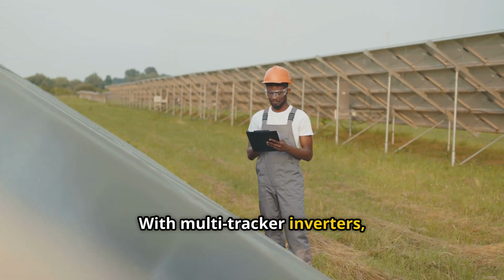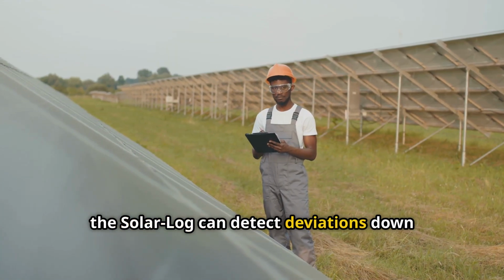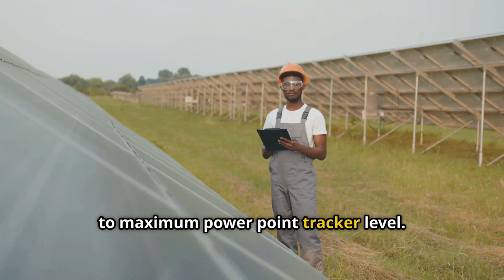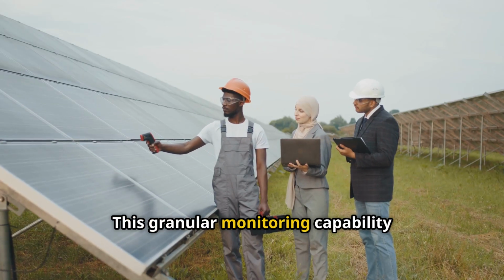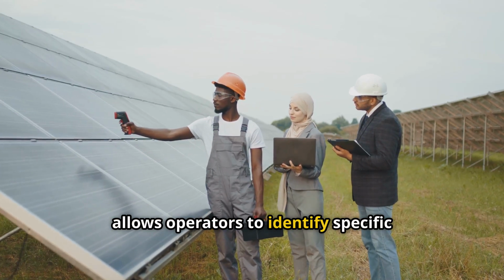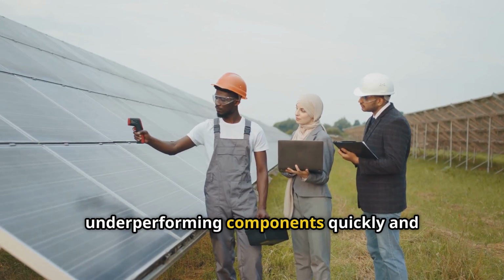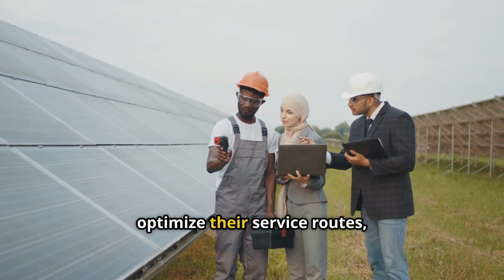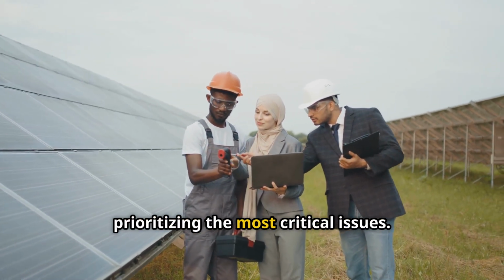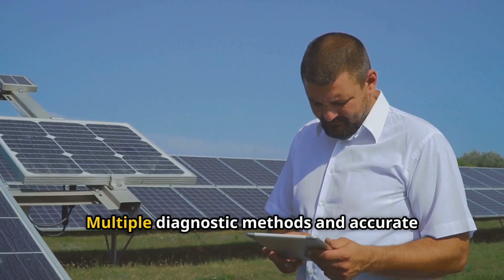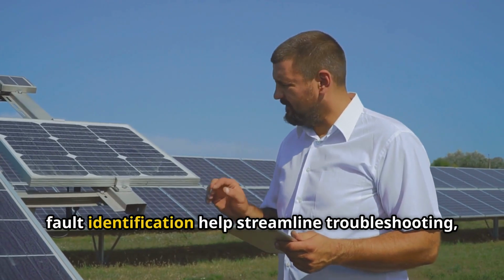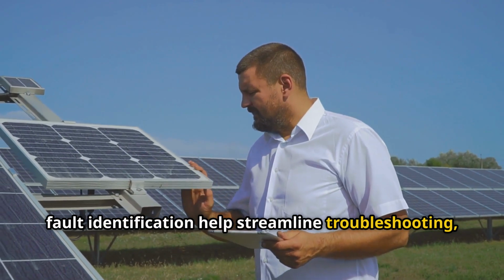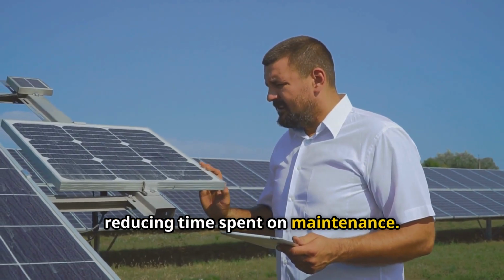With multi-tracker inverters, the SolarLog can detect deviations down to maximum power point tracker level. This granular monitoring capability allows operators to identify specific underperforming components quickly and optimize their service routes, prioritizing the most critical issues. Multiple diagnostic methods and accurate fault identification help streamline troubleshooting, reducing time spent on maintenance.